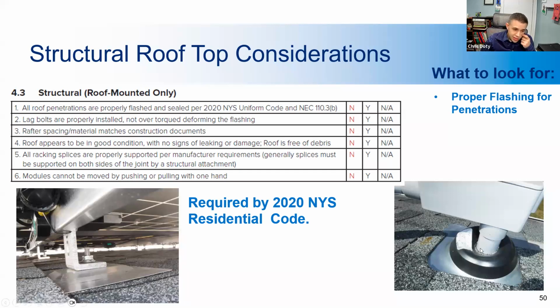And then on the right, you can see this is the correct piece of equipment that you would use for this, but it's not installed correctly and it would fail. It's pushed down. The rubber boot should be up, to shed water off of it, but it's been pushed down and water will collect there, and in the winter especially, it'll freeze and unfreeze as it gets warm and cold, and that'll cause damage to this penetration, and it could cause leaks and things like that. So eventually it'll fail, and so this would not pass inspection. It's a correct piece of equipment, but it's not installed correctly.